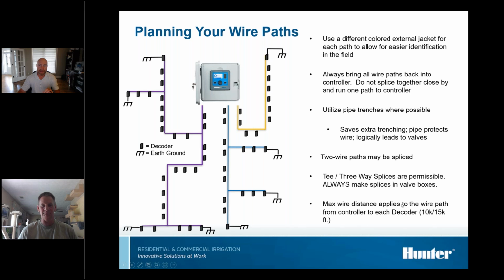Moving on, we talked about the max wire distance. That applies to the distance between the controller and the last decoder on the path. If you follow me here on this blue path, let's say we're using 14 gauge, you have 10,000 feet to work with. That would be 10,000 feet from here to here max, from here to here max, and from here to here max. So it's the furthest decoder away. That's your max distance. Like we talked about, 10,000 feet with 14 gauge, 15,000 feet with 12 gauge.